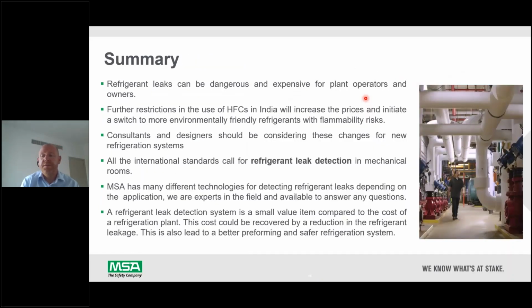So in summary of the presentation regarding leak detection, refrigerant leaks can be dangerous and expensive for plant operators and owners. Further restrictions on the use of HFCs in India will increase prices, like it has done in Europe and the US, and it will initiate a switch to more environmentally friendly refrigerants, which have this flammability risk. So you want to keep the gases in the system or install some kind of detection system.